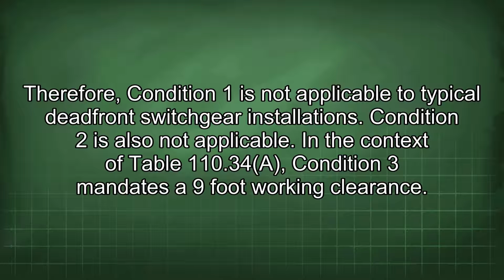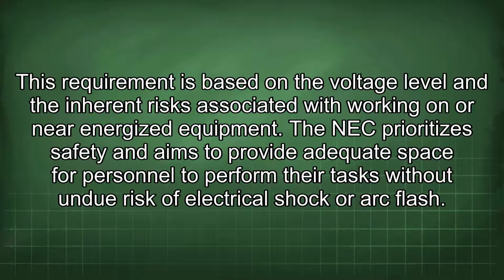Condition 2 is also not applicable. In the context of Table 110.34(A), Condition 3 mandates a 9-foot working clearance. This requirement is based on the voltage level and the inherent risks associated with working on or near energized equipment. The NEC prioritizes safety and aims to provide adequate space for personnel to perform their tasks without undue risk of electrical shock or arc flash.